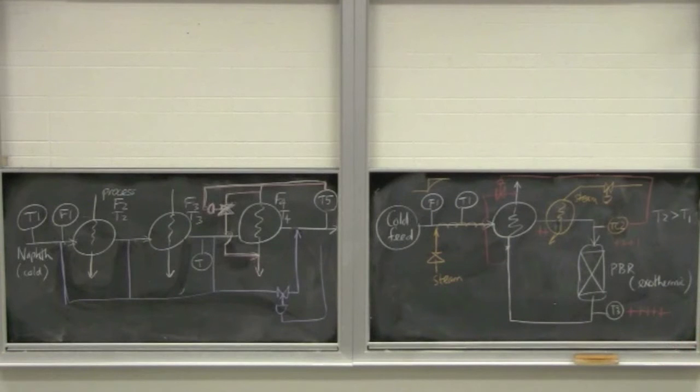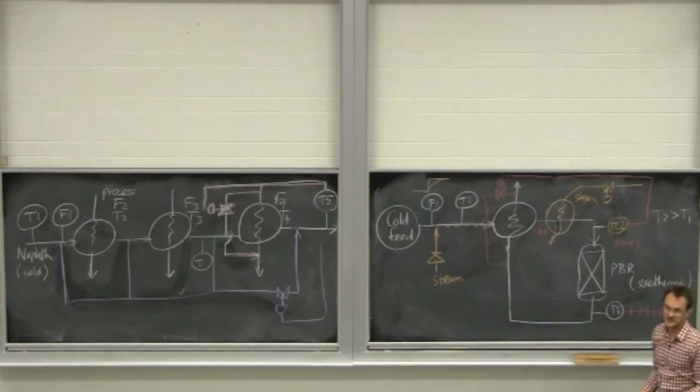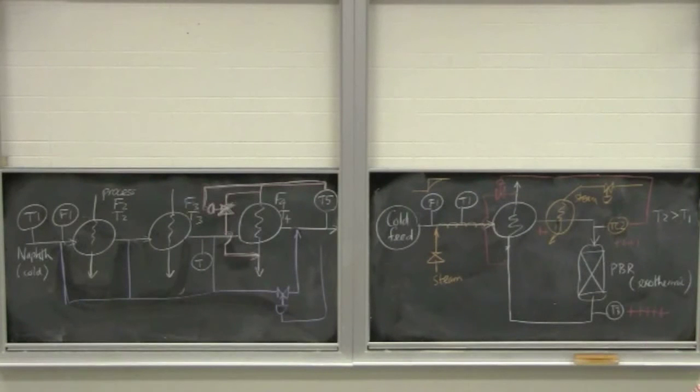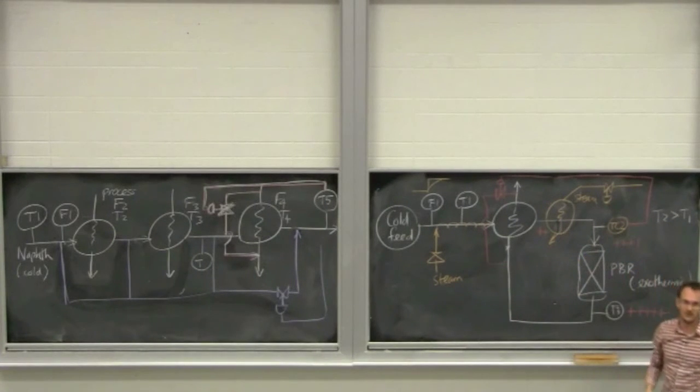So what bypass flow do you need would come into TC2. Okay. So this orange loop over here for steam is gone away. We've started up the reactor. We don't need that control loop anymore. So that control loop disappears. So once the process is up and running, we're still itch our control loop, same sensor or group of sensors because we would never control this important temperature sensor just on one sensor. Dr. Marlin mentioned reliability. We'd have a duplicate or even three sensors where we both take the votes from two out of the three sensors.